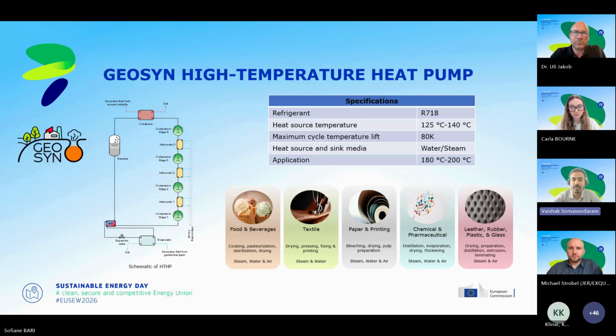Looking at the configuration, we have different stages of compression. We arrived at this configuration because of the properties of water, which has a very high discharge temperature that should not exceed the operating temperature of the materials used to build the compressor. So to keep the operating temperature well within the material's capabilities, we came up with this configuration having four stages of compression.